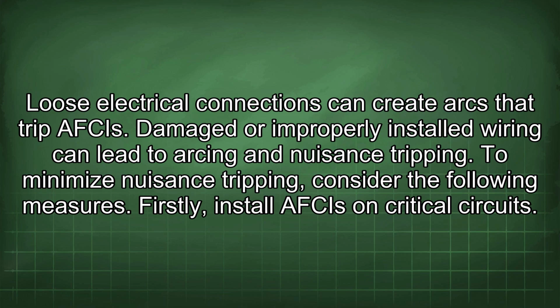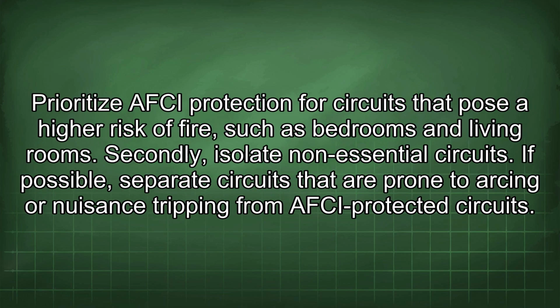To minimize nuisance tripping, consider the following measures. Firstly, install AFCIs on critical circuits. Prioritize AFCI protection for circuits that pose a higher risk of fire, such as bedrooms and living rooms. Secondly, isolate non-essential circuits. If possible, separate circuits that are prone to arcing or nuisance tripping from AFCI-protected circuits.